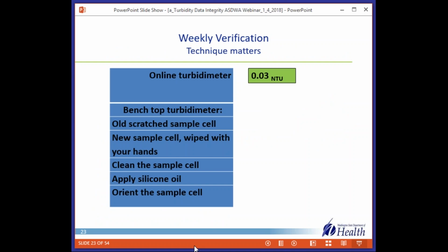So let me show you what happened when I did this. I started out and the online meter was reading 0.03 NTU. With the scratched sample cell, I got, what's that, 15 times the reading, 0.47. Then I switched to a new sample cell, but I wiped it off with my hands, and I dropped the turbidity in half. Then I cleaned the sample cell with deionized water and a lab wipe, and it dropped in half again. And then I applied a small amount of silicone oil, rubbed it on, wiped it off, and now I was down below 0.1. And then I tried orienting the sample cell, and I got it down to 0.08. So that's a good verification within 0.05.